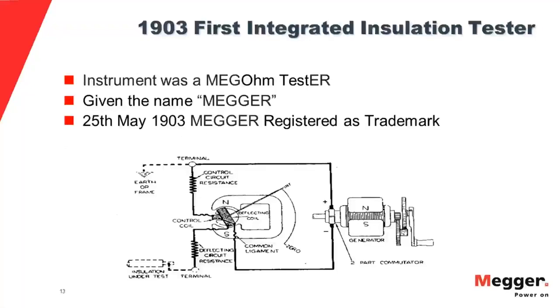And here's a look at that old circuitry then, with the hand crank generator serving as the power source. You've got the known circuit with the known resistor. You've got the deflection circuit with a kind of a stabilizing resistor in there, but the main component of that was the insulation under test. And they were working against each other and driving the pointer and reaching a compromise between the two forces that gave you your reading. And at that time, they trademarked the name Megger because it measured into megohms, or millions of ohms, and then that became the general industry name for an insulation tester, but the correct term for it is actually a megohmmeter, but it's so identified with our trademark that it's typically known as a Megger.